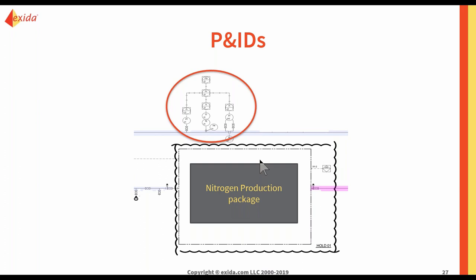The second and third revisions of the P&ID we received afterwards showed that they were actually trying to open a flow valve that suddenly popped up around this area. That is a very, very serious problem, because you are actually introducing a new failure point, and in a way, a new hazard. And if we just finished that hazard without relooking at the different revisions, without knowing that there's a new valve over there, then we are going to under-design the whole safety system. So that is a very, very horrifying consequence. But luckily, we caught that, and we were able to tackle this particular problem.